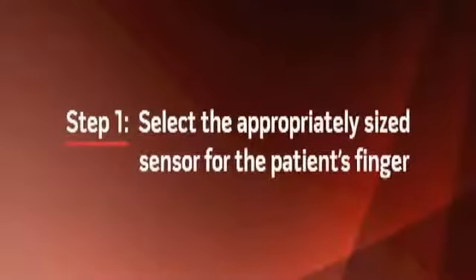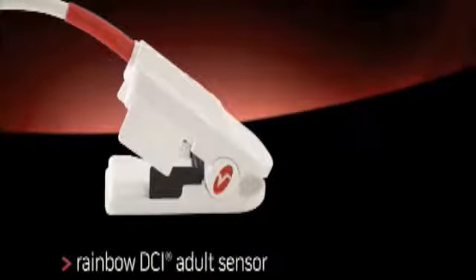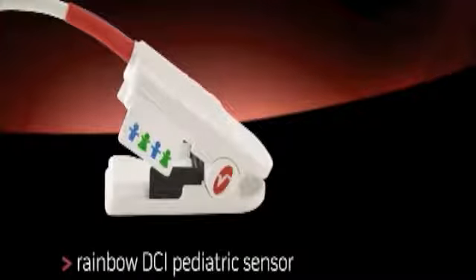Step 1. Select the appropriately sized sensor for the patient's finger. For adults with average to large sized fingers, use the adult sensor. For patients between 10 and 30 kilograms, and for adults with slender fingers, use the pediatric or small finger sensor. The rainbow sensor should be used on fingers only. Using the rainbow sensor on toes or earlobes, even on pediatric patients, will cause inaccurate readings.